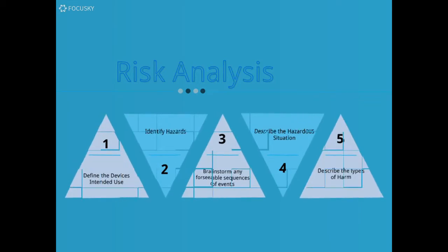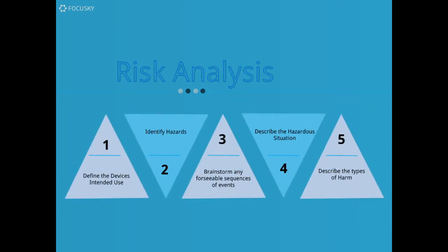Risk assessment. We're going to start by defining the device's intended use, identify the hazards next, then brainstorm any foreseeable sequences of events. Describe the hazardous situation, and describe the types of harm.